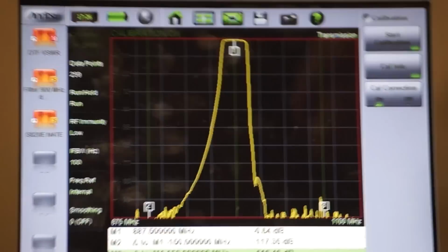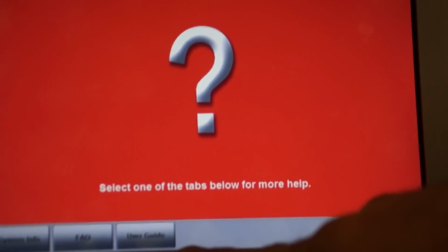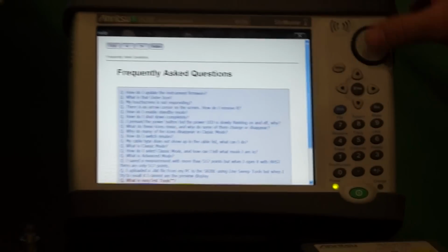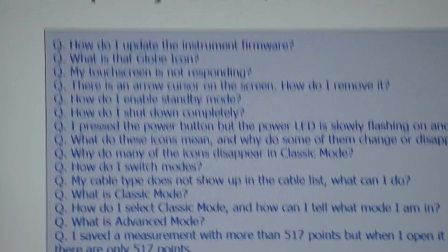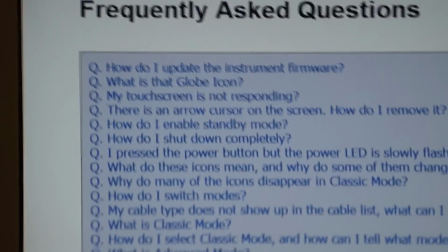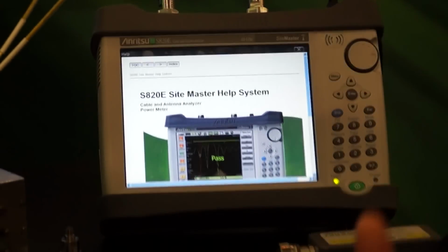The instrument's calibration menu will walk you through the calibration process, and even shows you guided pictures as you go. Other new features on this particular instrument: we've built in a help menu. There is system info that gives you a quick view of the status of the unit, firmware, temperature, those types of things. There are also frequently asked questions in case you're wondering about certain things on that particular instrument. These are dynamically linked to the actual user guide, which is also built into the instrument. So the entire user guide now comes with the product. You don't have to carry that book with you any longer.